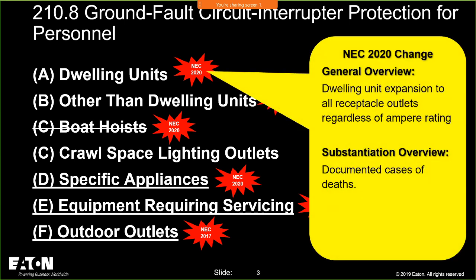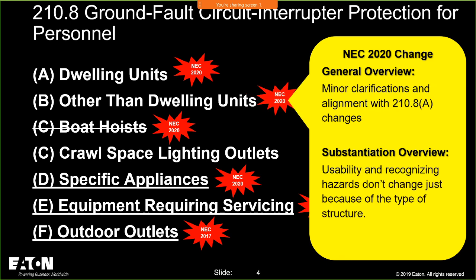So what we did in dwelling units, basically, the question arose, remember we only had 15 and 20 amp circuits. Then we moved the other than dwelling units requirement up to 50 amp single phase and 100 amp three phase. Well, we asked the question in dwelling units, and we said, you know what, we don't care what amp rating the receptacle is. If it's in any one of those locations, it's going to need to be GFCI protected. And I think that's a significant increase in coverage, taking you above the 15 and 20 amp in dwelling units. We'll cover that a little bit more.